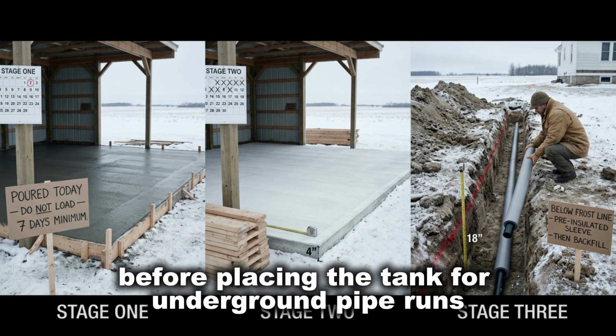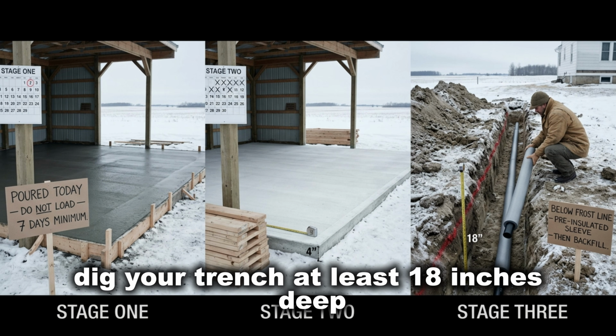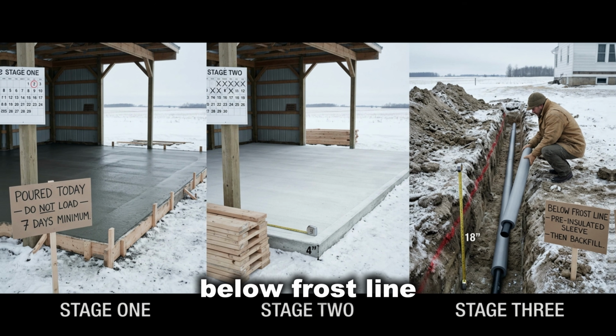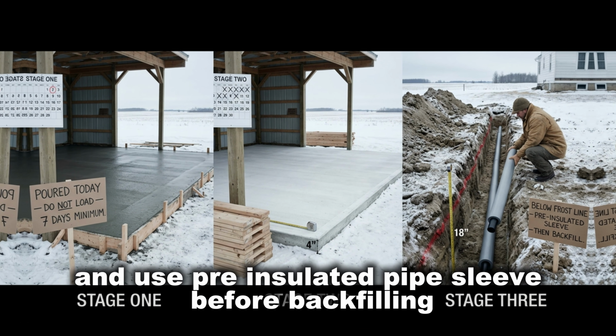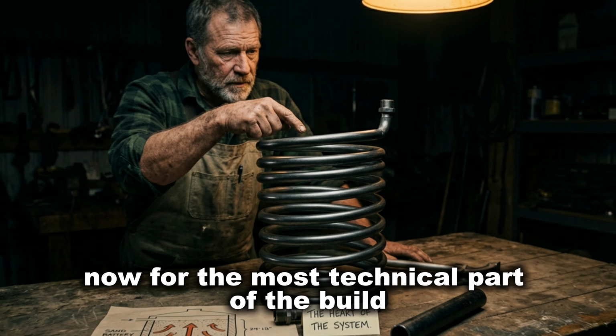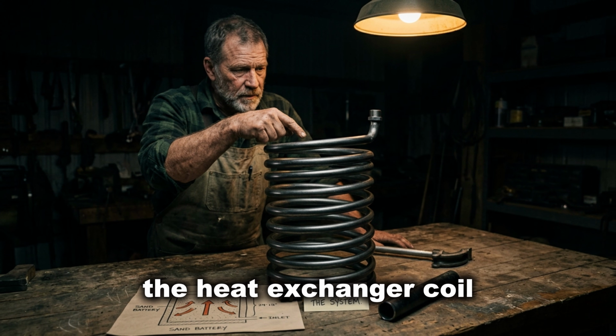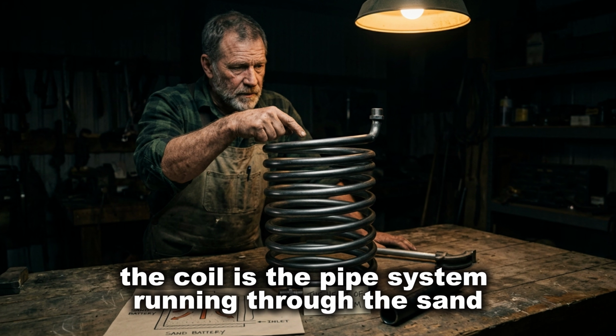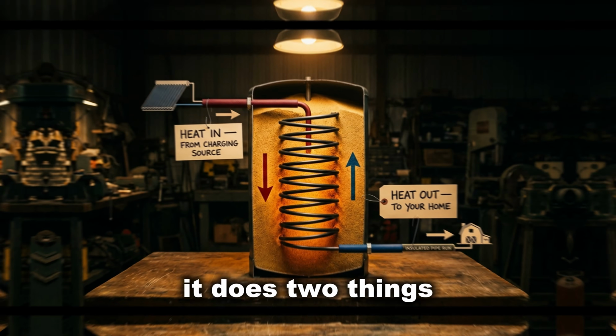For underground pipe runs, dig your trench at least 18 inches deep, below frost line, and use pre-insulated pipe sleeve before backfilling. Now for the most technical part of the build, the heat exchanger coil. The coil is the pipe system running through the sand. It does 2 things.